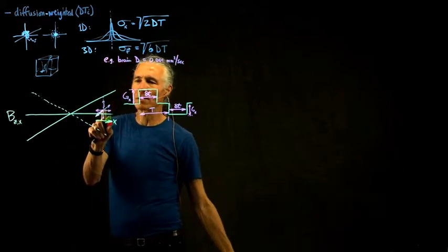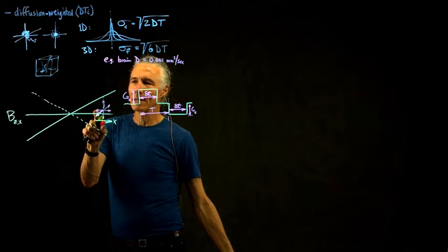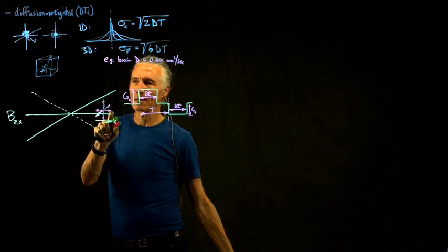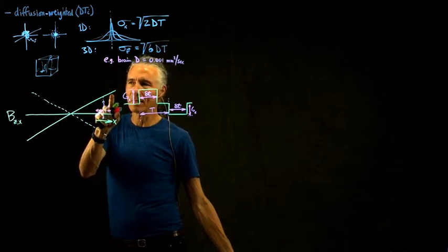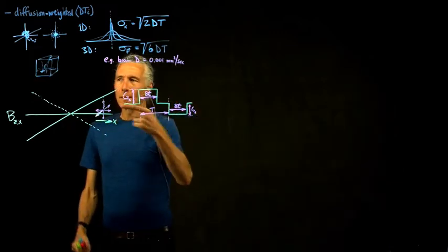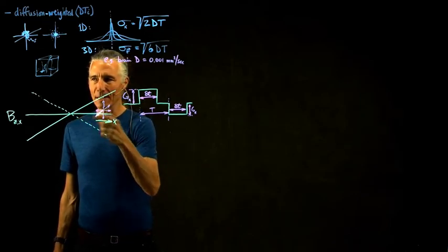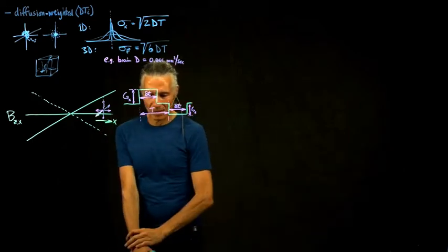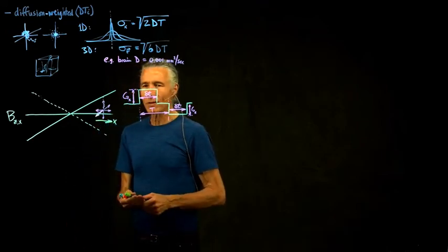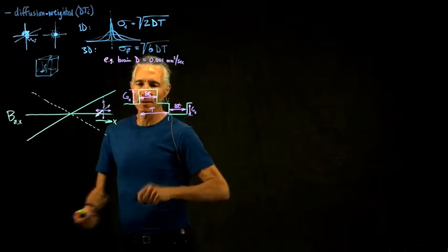If it moved a certain distance in the negative x direction, the gradient is going to fix it a little bit, but not too much. But if you went the exact opposite direction, it's going to fix it exactly the same amount. And so we can't distinguish which direction the diffusion went, we can only distinguish the axis of diffusion. We can't distinguish the actual direction, like minus x or x. So that's the fundamental way that you actually measure it.